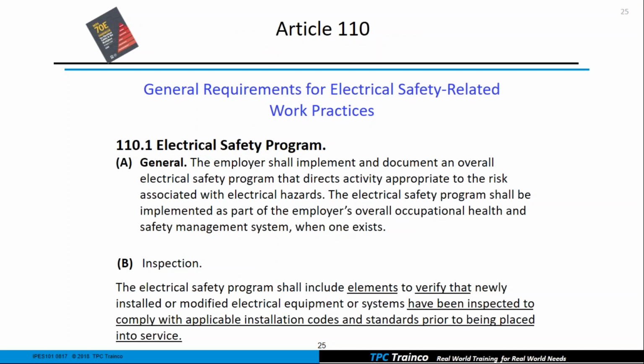In the electrical safety program, in 110.1b, you can see inspection. So now, if I have some newly installed equipment or modified electrical equipment, I've got to make sure it's been inspected to make sure that it complies with the National Electrical Code, the manufacturer's recommendations, any other standards that might be out there prior to being placed into service. So I'm not sure if you understand this part or not, but OSHA loves everything documented, right? So when this inspection occurs to equipment that was newly installed or modified, I would make sure that we documented that inspection. Now, that could be a self inspection.